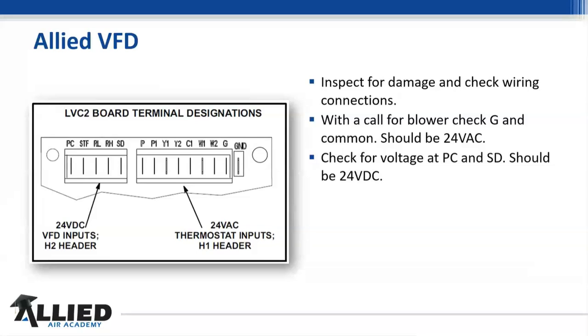And there's the STF and RL and SD and all that good stuff. But you want to inspect it for damage. That's kind of a duh. And then you want to call for the blower. And you should get 24 volts between ground and G on here. If we just energize G, so we can go to this board and measure it, and we got 24 volts, we know we're good. We've checked the voltage on the inverter, the high voltage on the inverter, and we'll make sure we're good to go.